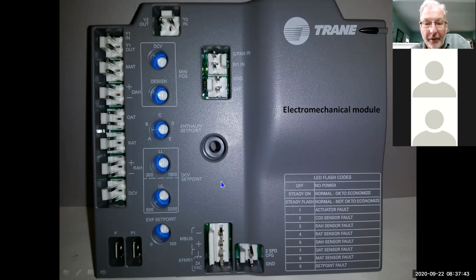A lot of places are not using it at this point, but if this is connected, you're going to have to make some adjustments to these demand control ventilation points. The EXF set point, that's for your power exhaust. So if you have a power exhaust on this and you set this to 0, it'll probably run mostly all the time, anytime you get a call for fan or economize. Otherwise, if you set it to 50%, when the damper gets to 50% open, it'll bring on exhaust fans, power exhaust. And that's basically how the economizer sets up.